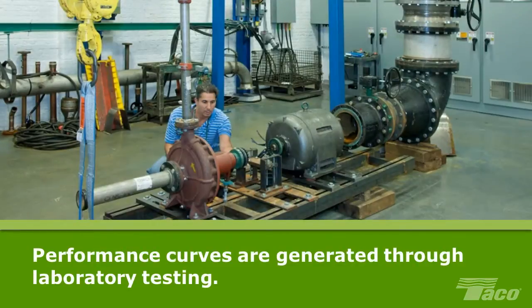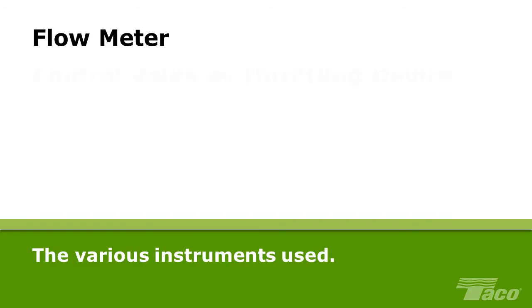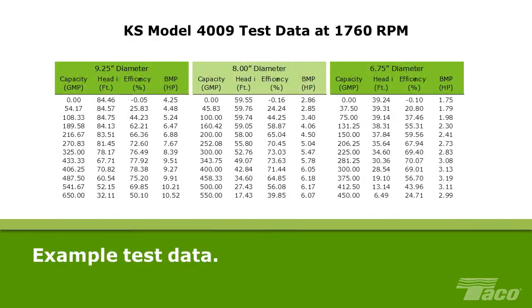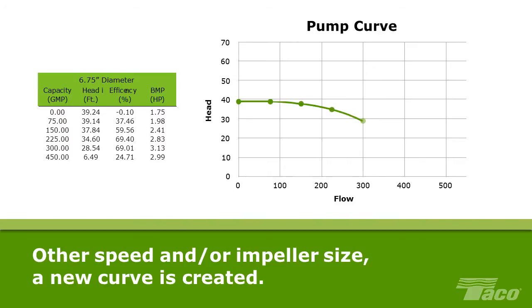Pump Curves. Pump manufacturers generate pump performance curves by laboratory testing. The pump is mounted in a test stand with pressure sensors before and after the pump, plus a flow meter, a control valve or throttling device, a tachometer to confirm pump speed, a torque cell to measure horsepower, and a data acquisition console. Here's example test data from a Taco KS pump tested at 1760 RPM, focusing on one impeller diameter — 8 inch — and 6 operating points. This data enables us to plot a performance curve for the KS4009 at 1760 RPM. At any other speed and/or impeller diameter, a new pump performance curve will be created.